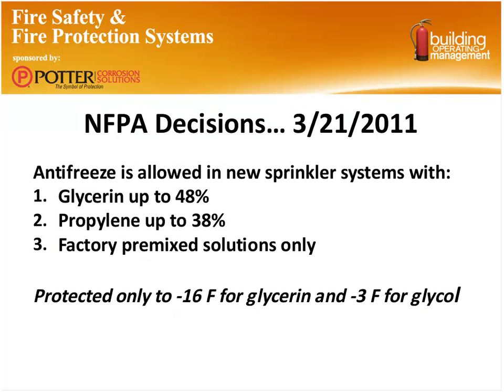So what NFPA came up with in 2011 were these recommendations: that the antifreeze systems with glycerin be limited to a 48% concentration. In the propylene glycol-based mixes, a 38% concentration. And number 3, that factory premix solutions only be used to protect these different types of systems from freezing. Well, there's an issue with that.